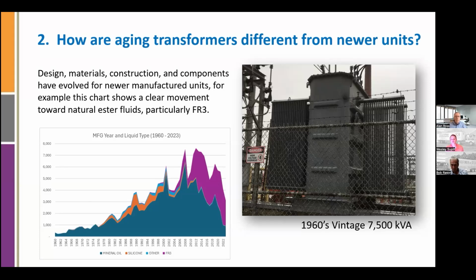So this is just one example to show how components change over time and how we're not trying to articulate one as bad and one as good necessarily, but how you need to consider those components in how you maintain them, sample, test, those kinds of things. And then, like just the design and style of a 1960s era model. The radiators are different than what we might see today. The style is different. And now a 7.5 MVA or 7500 kVA unit may be a cabinet style design with panels that you open. So just articulating the differences between an older unit and a newer unit.